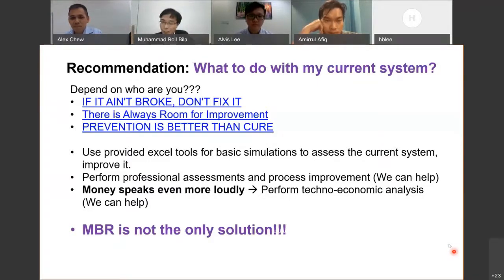So basically in MBR, we force the microbes not to reproduce. Because the food is less, they will preserve the food inside the cell instead of reproducing more cells. The logic is that when microbes barely survive, they won't be able to multiply. But the scientific answer is the KD, the decay coefficient, which is higher for MBR. A very good question.